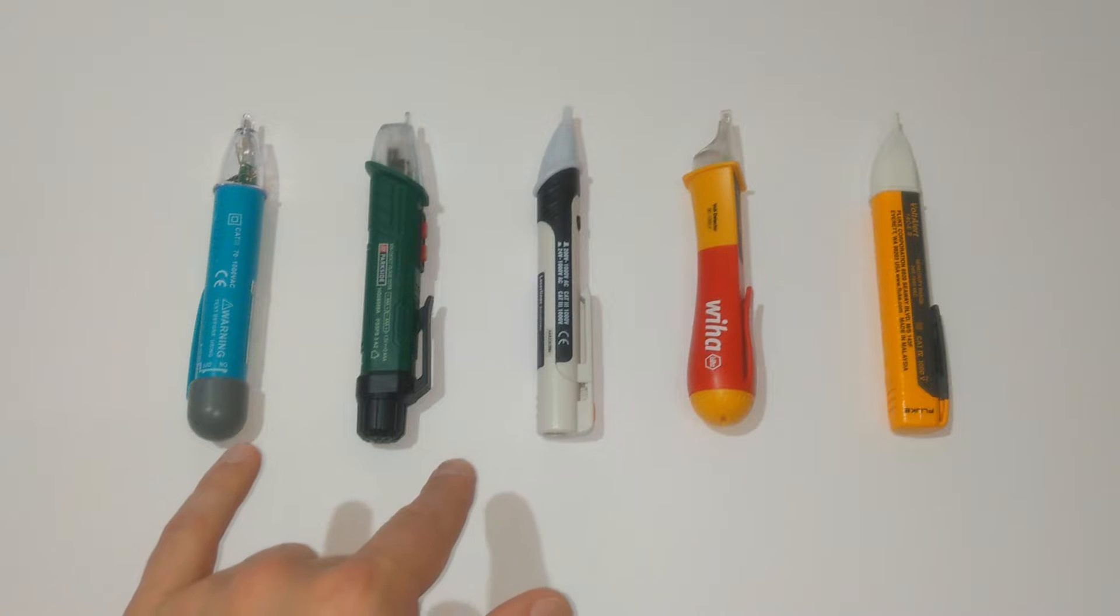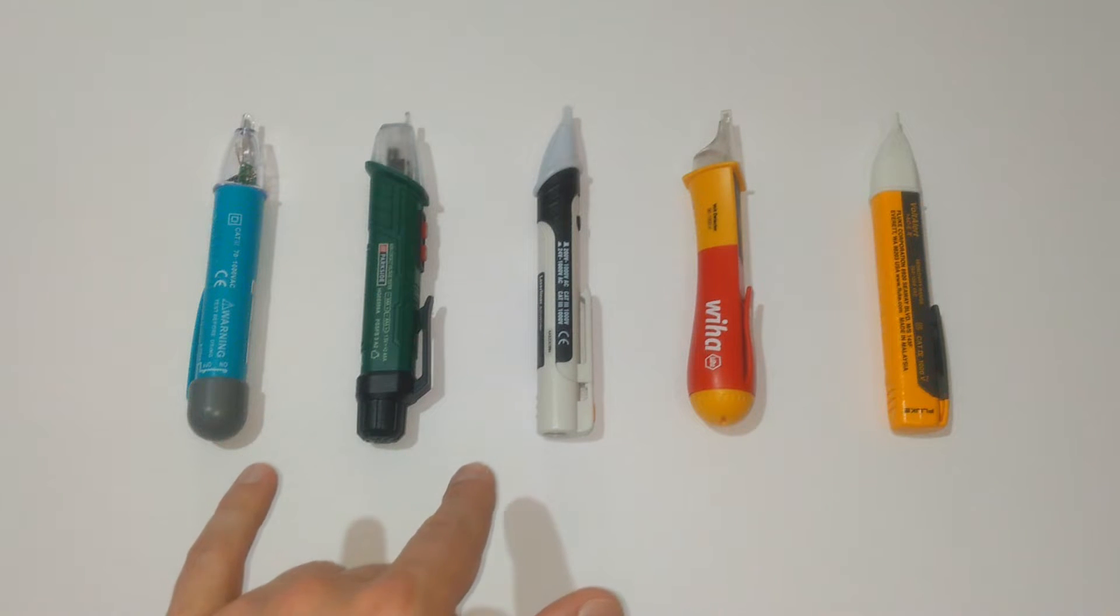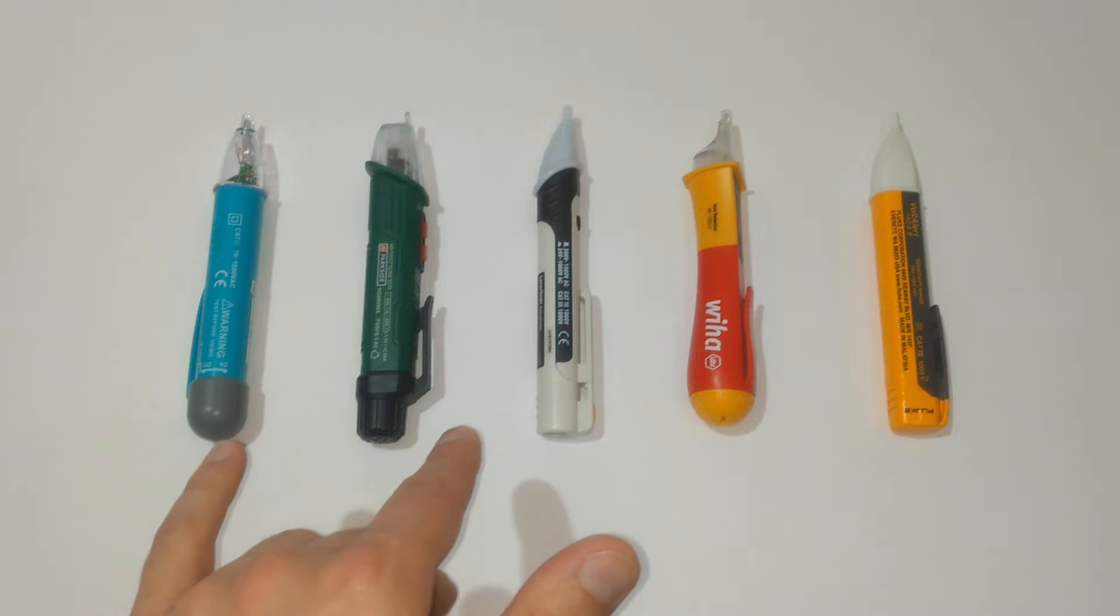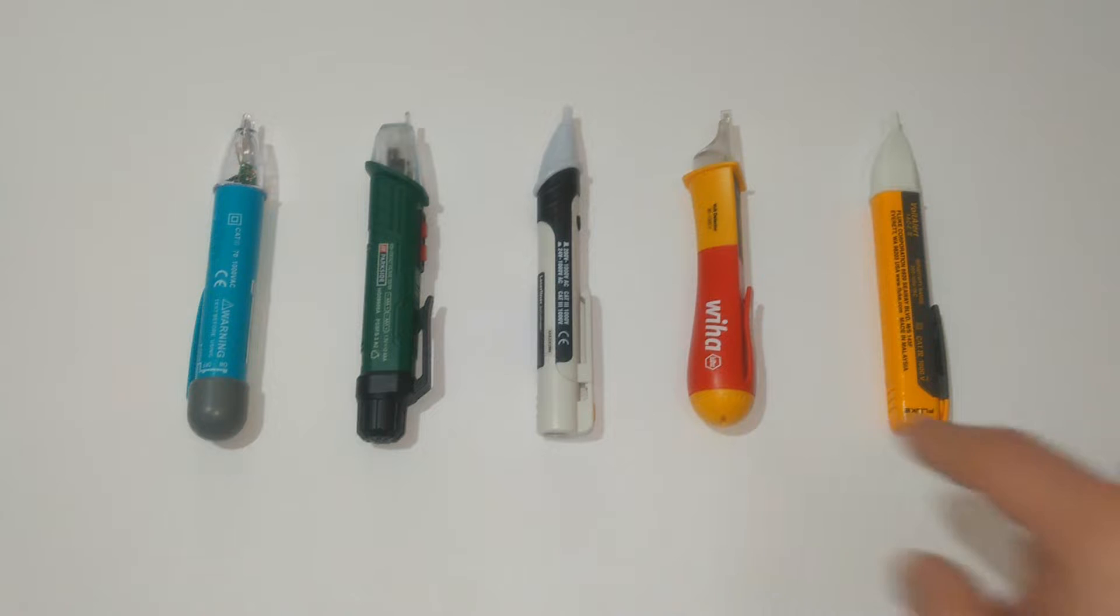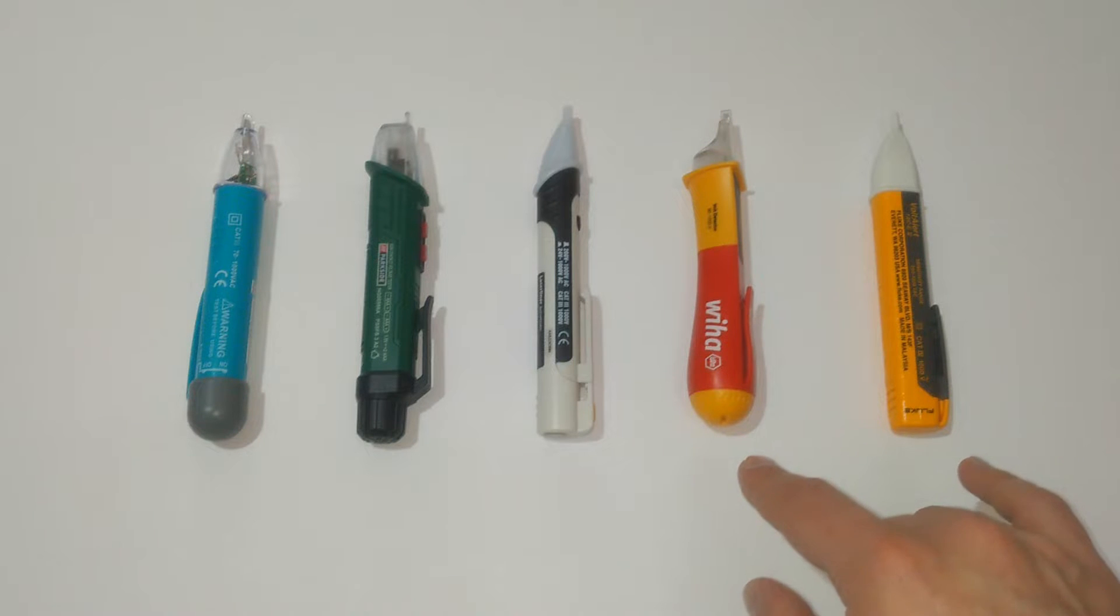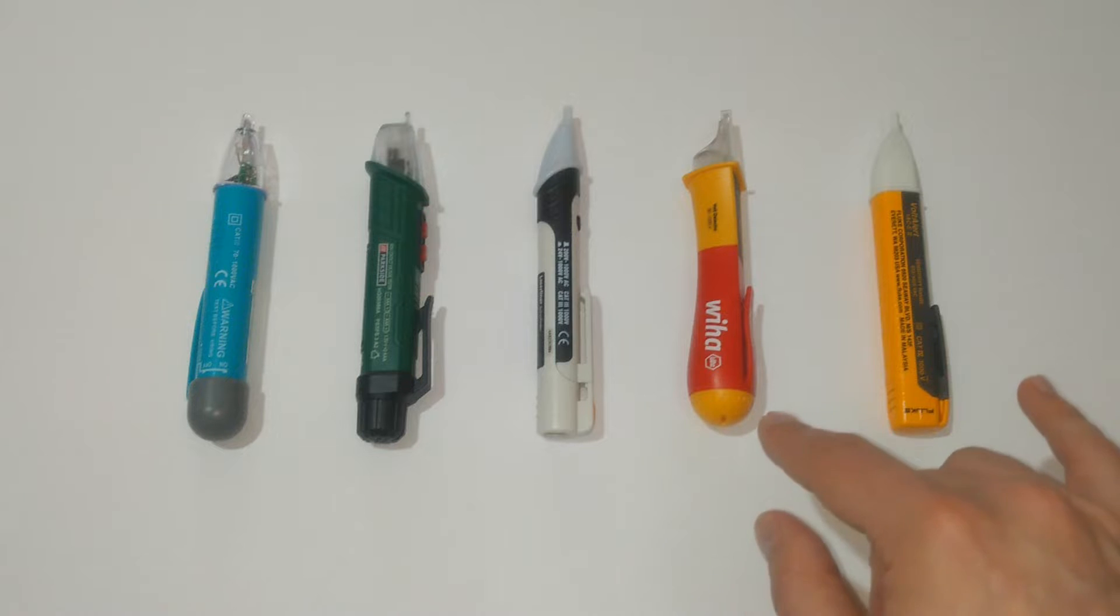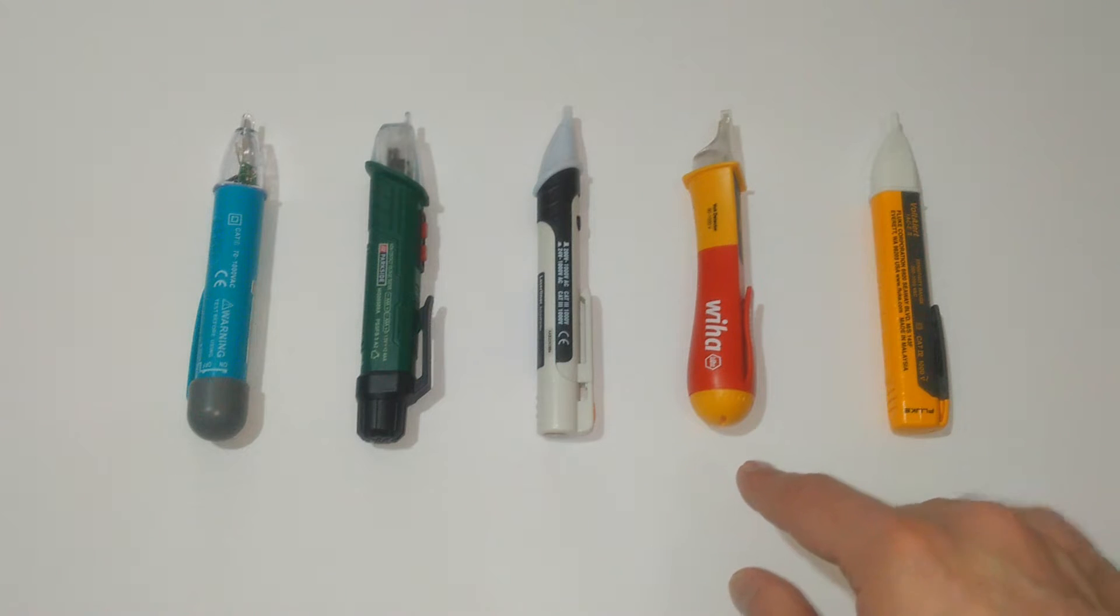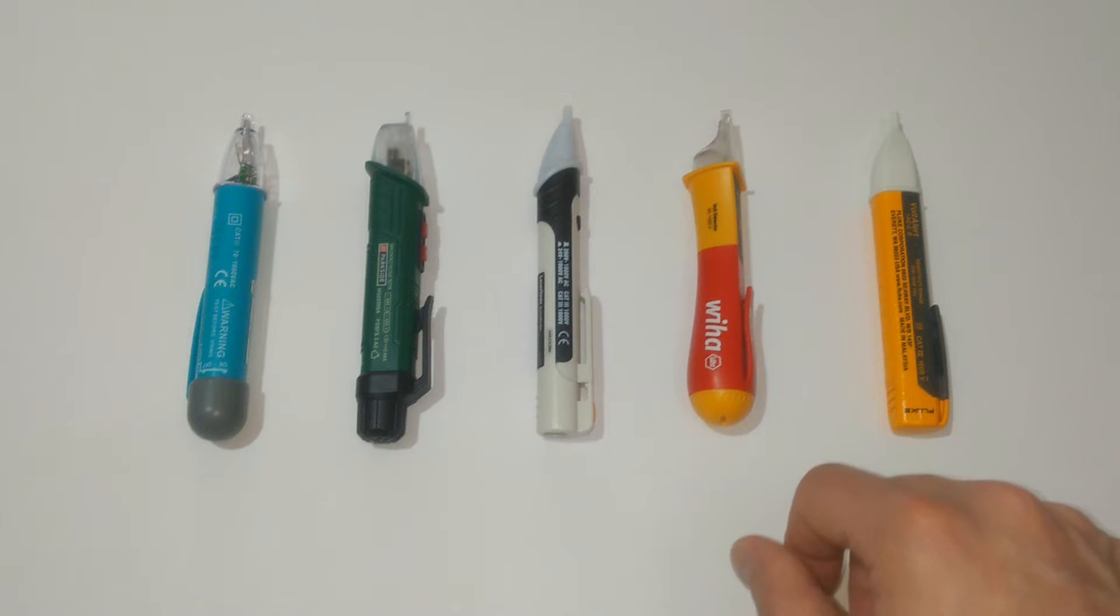The first three are rated measurement category 3, meaning you can use them for measurements on your household or building installation right after the main circuit breaker, while the Fluke and the Wiha are rated measurement category 4 and that's why you can use them for measurements even at the power source of the installation. They have better insulation and better resistance to impulse voltages.